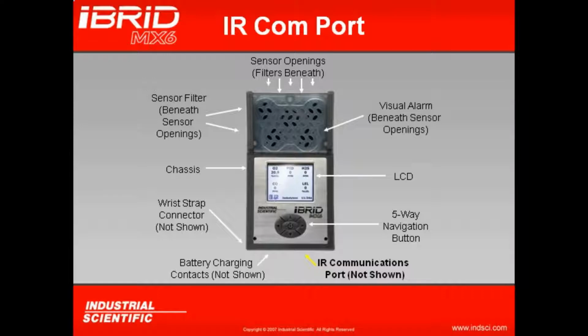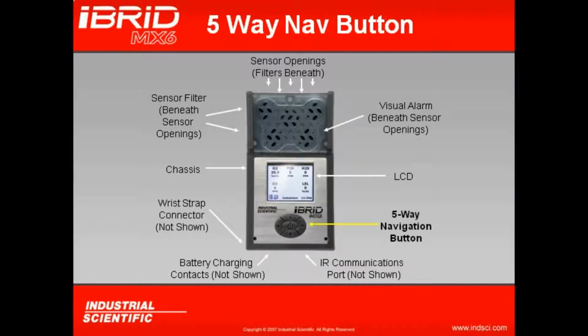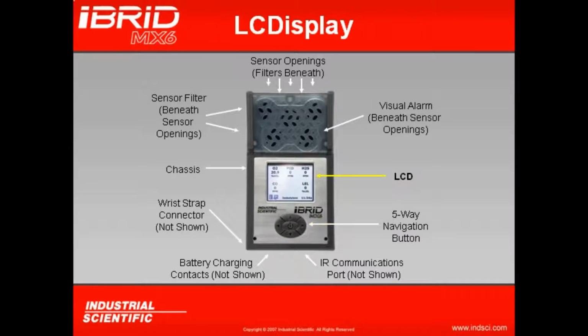Right next to that is the IR communication port. This is for communication with the data link or when connected with the DS2 docking station. There's a 5-way navigational button that allows the user to navigate through the different operations of the MX6. At the center of the instrument is your LCD display. At the top of the instrument, underneath that opening, is where your visual indication of alarm condition is. Whenever any one sensor goes in alarm, all 4 LEDs will start to flash.